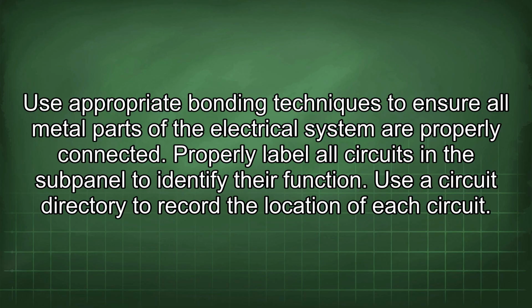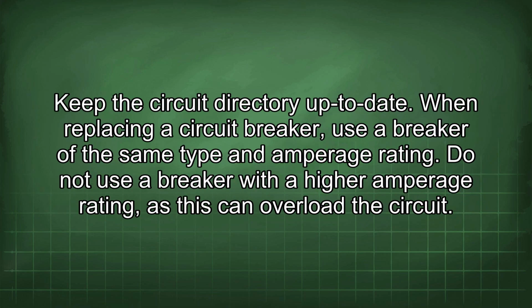Properly label all circuits in the subpanel to identify their function. Use a circuit directory to record the location of each circuit. Keep the circuit directory up to date. When replacing a circuit breaker, use a breaker of the same type and amperage rating. Do not use a breaker with a higher amperage rating, as this can overload the circuit.